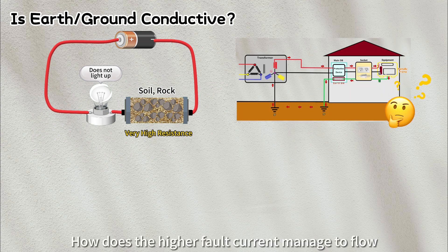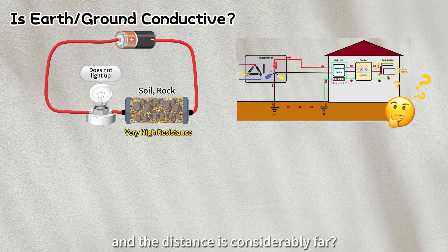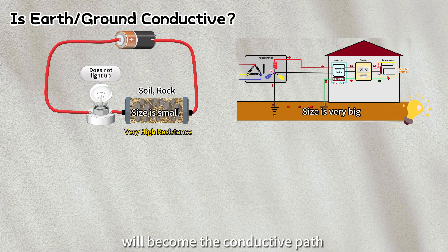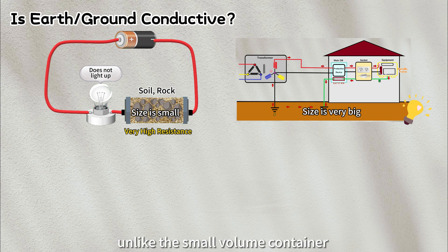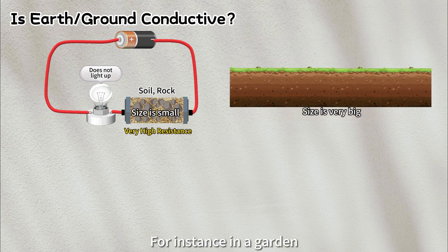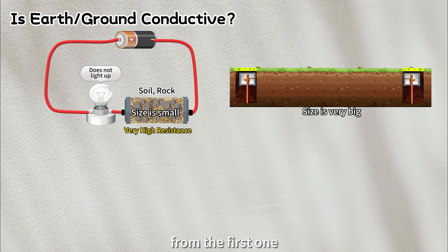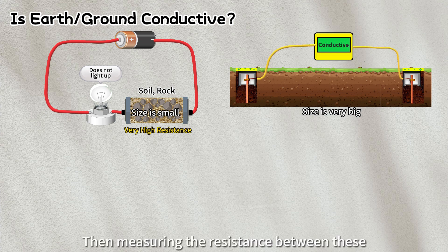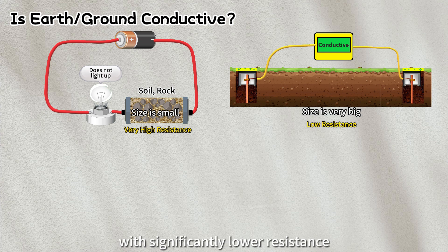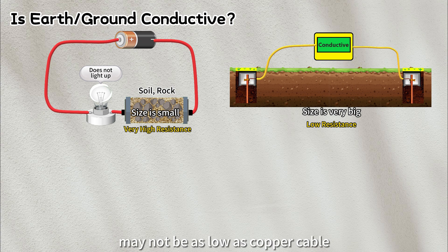This may prompt you to wonder, how does the higher fault current manage to flow when the soil in the ground has very high resistance, and the distance is considerably far from our house to transformer station? In fact, the soil or ground will become the conductive path when the size involved is very huge, unlike the small volume container used in the previous experiment. For instance, in a garden, if we insert an earth rod into the ground and position another earth rod at a certain distance from the first one, then measuring the resistance between these earth rods will indicate a conductive result with significantly lower resistance. Although the ground resistance value may not be as low as copper cable, it is still sufficiently small to allow higher fault currents to flow.